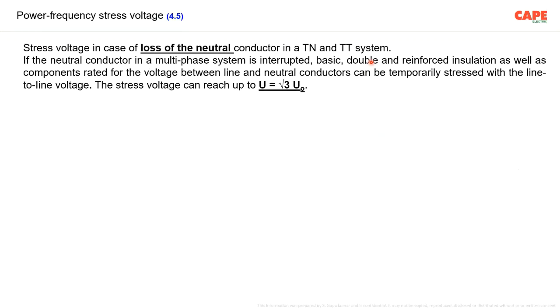The other issues are, the first issue is a high voltage fault. The second issue is the loss of neutral. In case of a loss of neutral, it is nothing but a neutral disconnection between your house and your transformer, the transformer supplying energy to your electrical installation. Some of the phases may experience a voltage between phase and neutral up to 1.73 times U0. So approximately about 440 volt or 400 volt can be experienced.